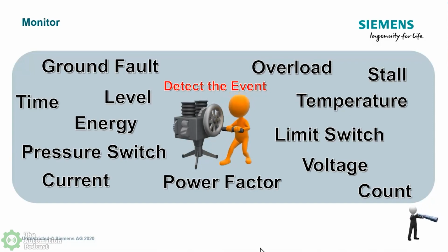And then of course, stalled rotor, we could do that if you're doing maybe a fire pump application. And then we also have time. I had another opportunity a few years ago where a customer wanted to minimize how many times that pump was turned on, and he only wanted to allow 5 times in a half hour. And so SIMOCODE has the ability; it lays dormant, it doesn't turn on unless you want it to, but you have the ability to put in how many times you want the motor to turn on within a time period.